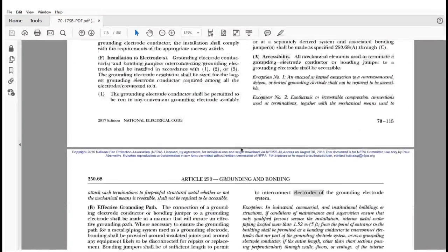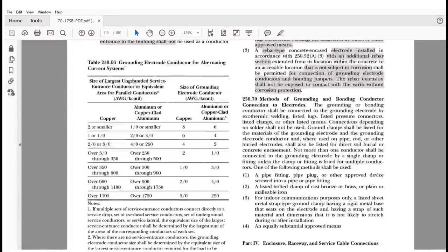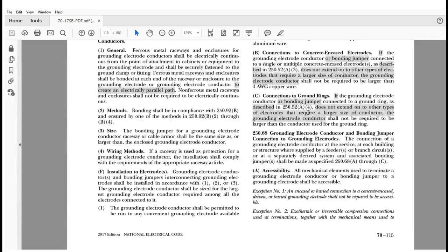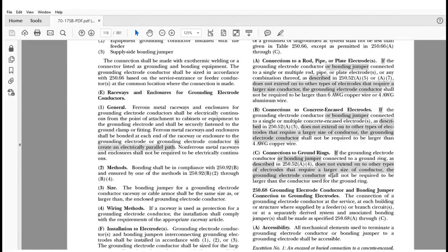In other words, I didn't need to go to this table right here and deal with that based on the largest ungrounded service entrance conductor or equivalent area if they were parallel. So all of set A, for example, or B or C, whatever that type. I didn't need to go here because I had the provisions that were provided for me back here. Okay. The importance of this is it made it clear, and here's the part you want to read. Here's the most important part. Let me go on and read it because it applies to all of them, but really take this in because there's been a lot of confusion on this sole connection language.